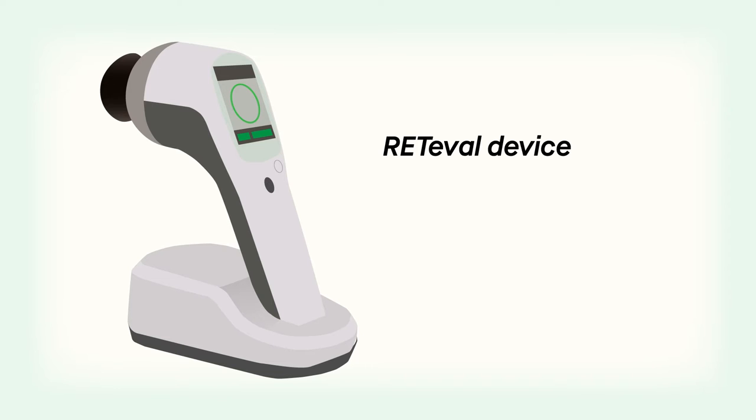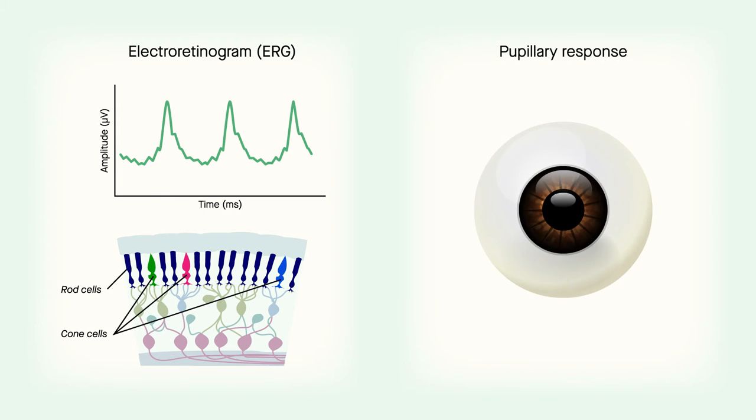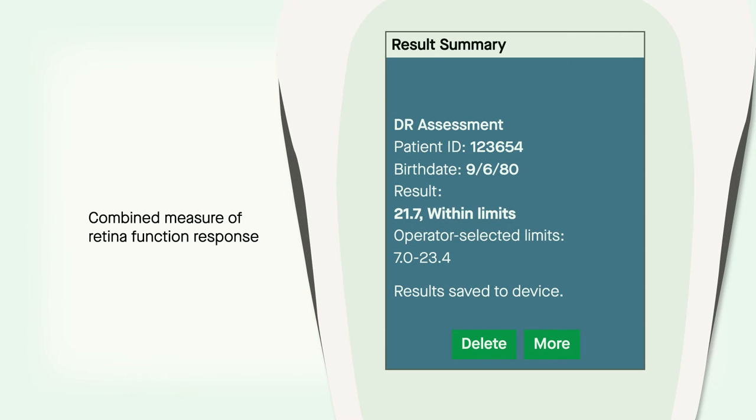Unlike fundus photography, which assesses structural features, the RETeval device measures the function of the retina in two distinct ways. One is through an electroretinogram, or ERG, which measures the functional status of the rods and cones, much like an electrocardiogram. And the other is the pupillary response. The RETeval device combines these responses into a single number called the DR score.